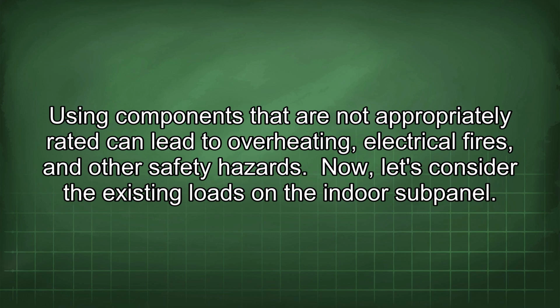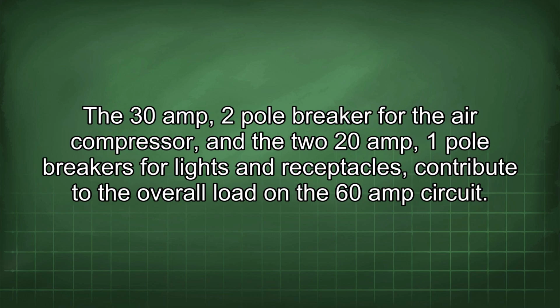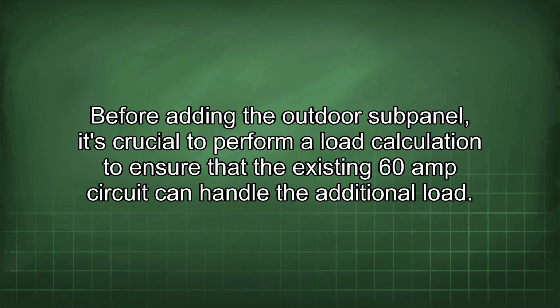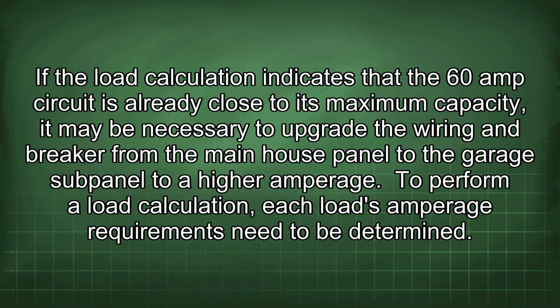Now, let's consider the existing loads in the indoor subpanel. The 30-amp 2-pole breaker for the air compressor and the two 20-amp 1-pole breakers for lights and receptacles contribute to the overall load in the 60-amp circuit. Before adding the outdoor subpanel, it's crucial to perform a load calculation to ensure that the existing 60-amp circuit can handle the additional load. If the load calculation indicates that the 60-amp circuit is already close to its maximum capacity, it may be necessary to upgrade the wiring and breaker from the main house panel to the garage subpanel to a higher amperage.